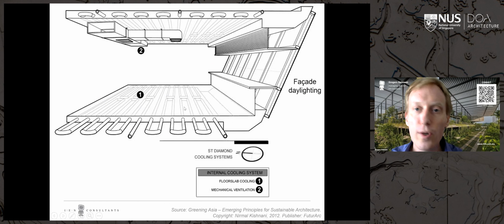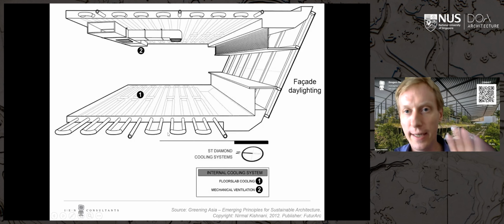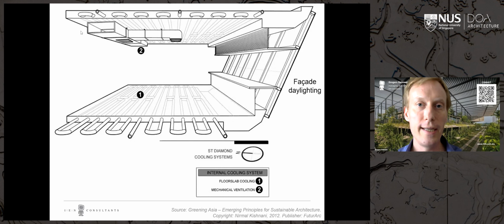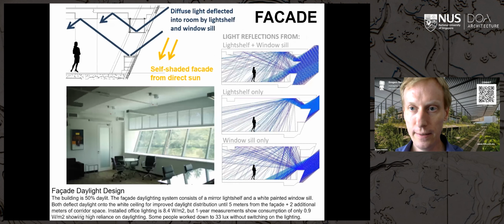So 40% of the cooling of the building comes from these pipes, and this cooling is done at night, which I'll talk about a bit later. These pipes can only do the sensible cooling and not the latent cooling, so that means they can't dehumidify. So you still need normal air conditioning to do the dehumidification. Maybe I'll just go back.